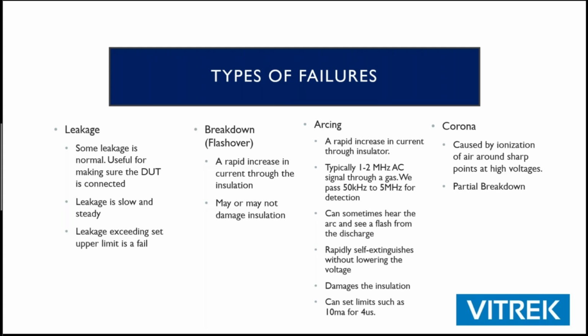If you're using breakdown only, which is a feature that's standard in the V7X, there's a couple things there. Once again, your product could be breaking down, or your product could be drawing more current than we have set up around our breakdown only test. So definitely check with us if you're seeing that. You could have arcing. Depending on the sensitivity that you set your arc circuit to, you may or may not fail on that arc. And then corona is another issue also. You're really not going to see it as bad at the voltages in this consumer product category, but once you start getting above 2000 volts, it can become an issue, and it could certainly make the difference on a pass or fail.